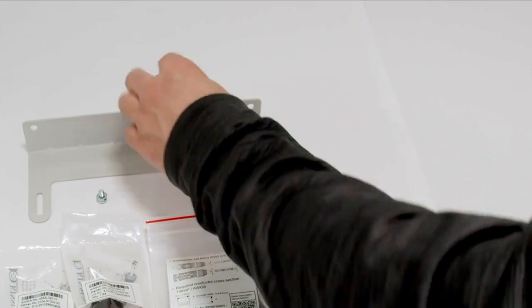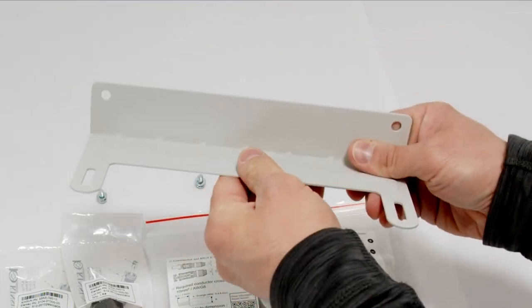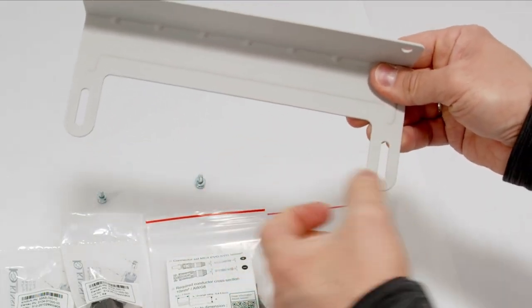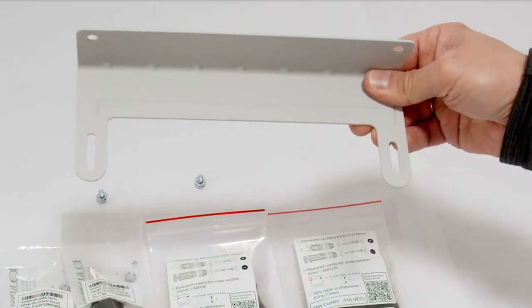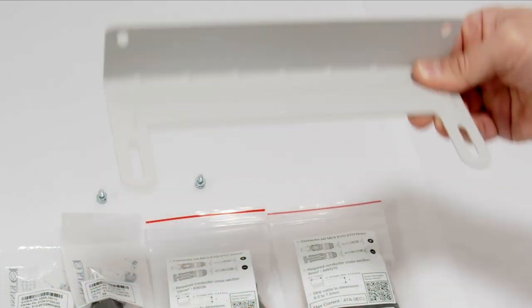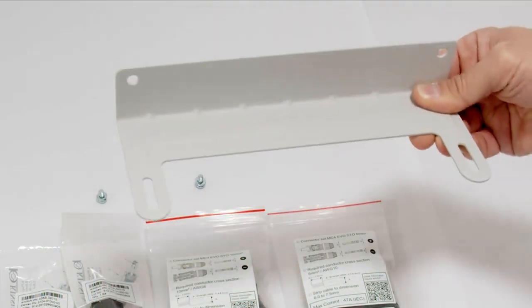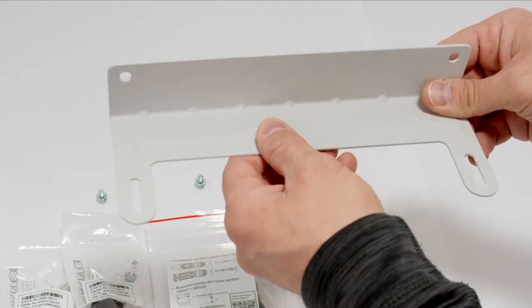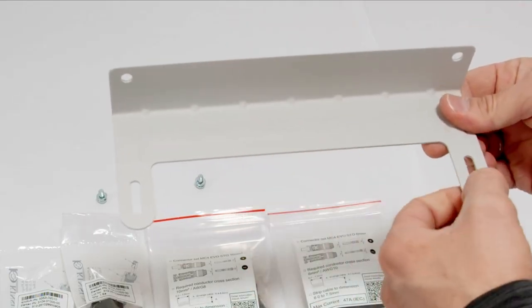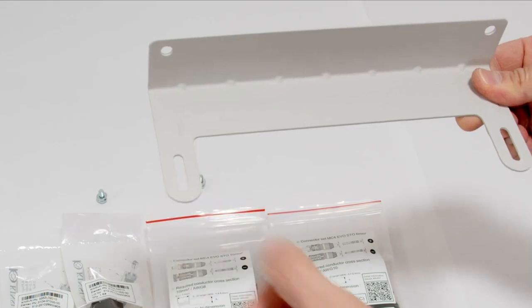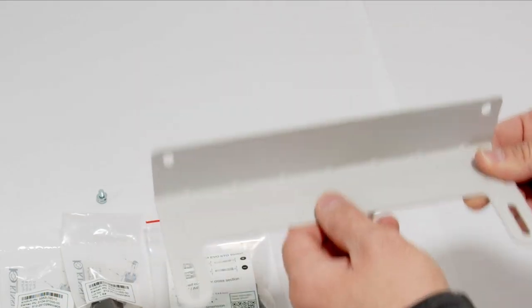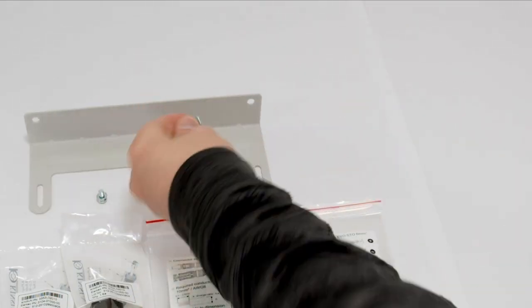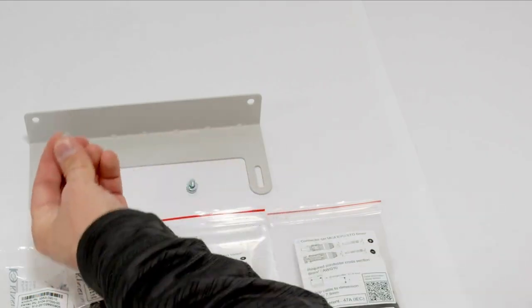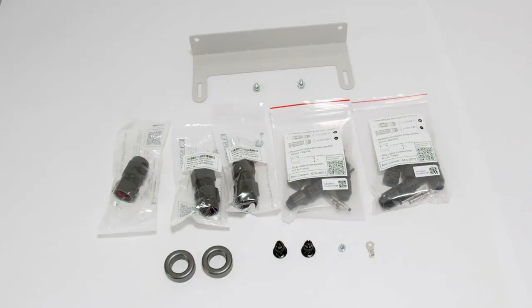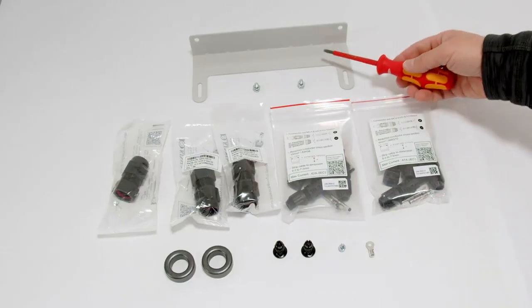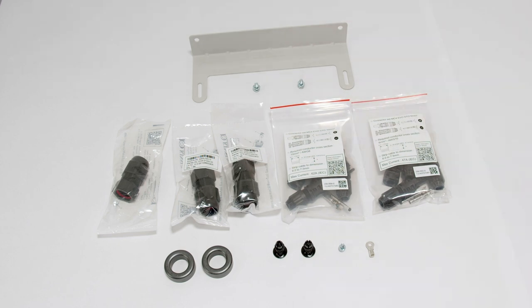For mechanical reasons, we have our wall mount within scope of delivery, and as you can see with these mounting handles here, you can adjust them in the depth of the system. So depending on how far the battery system is installed away from the wall, you have a little bit of possibility here to change that. Furthermore, there are two screws in scope of delivery to screw down the wall mount to the battery system itself. This is then installed on the battery management unit.